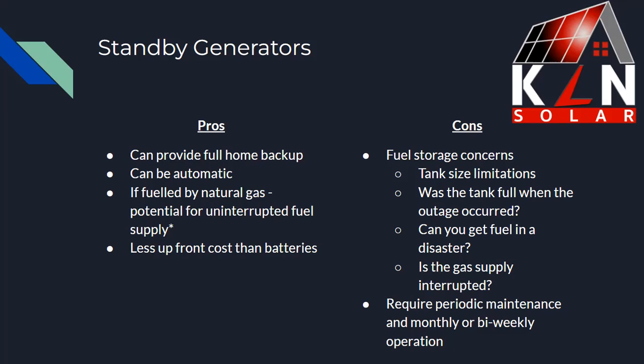In terms of cons, we already talked about fuel storage concerns. How big of a tank can you realistically put by your house? Is it going to be a buried propane tank? Those can get expensive. Is it above ground? Is it a diesel tank? And was the tank full when the outage occurred? Everyone likes to think, okay, this propane tank will give me 4 or 5 days of backup. That's assuming you had a heads up and were able to fill your tank before the storm hit. If you're running off a propane tank that your house also runs on, there's a good chance you're not full to begin with.